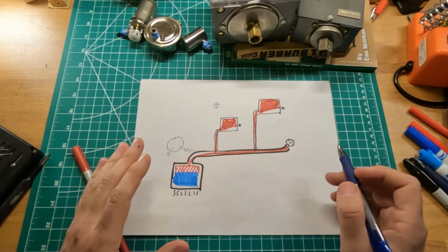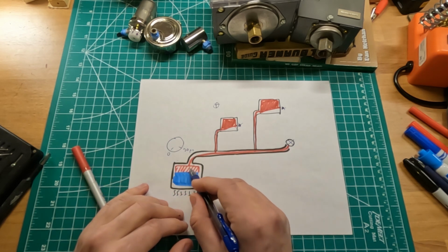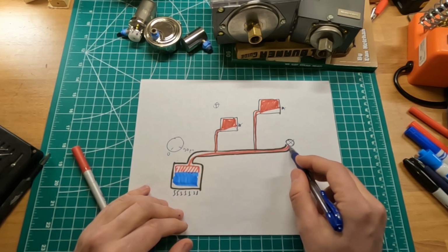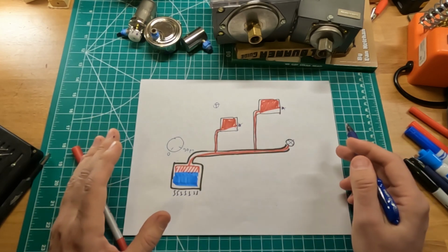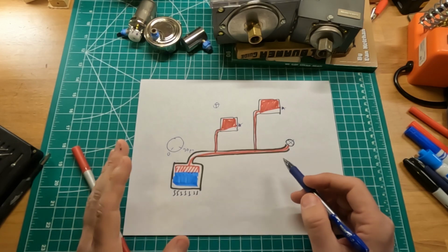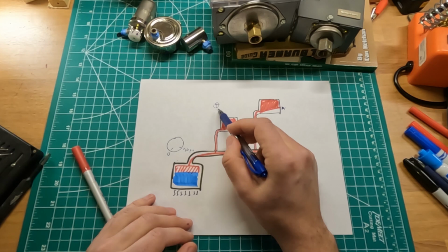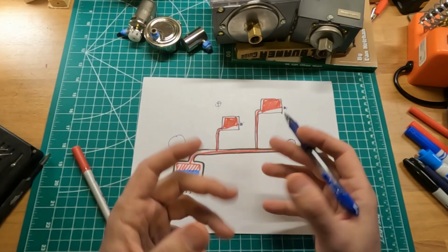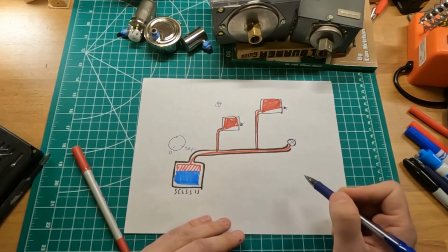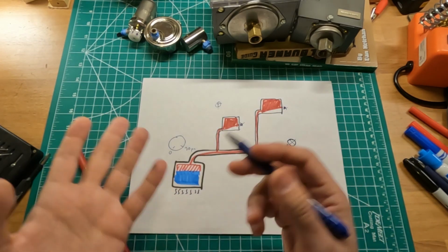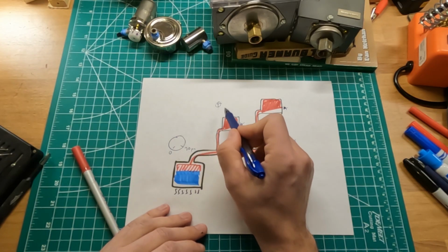In other words, in a perfectly working system where everything works the way we intended, the pressure should never build up. The moment you build up any steam inside the boiler, it travels to the end of the main, or to one radiator, to another radiator, however many radiators you have. The pressure only starts building up when the thermostat keeps on calling for more temperature. And again, it could be for all sorts of reasons. Maybe you set the temperature very high, or maybe you have a window open next to the thermostat and it's a cold day, so the thermostat is never satisfied.